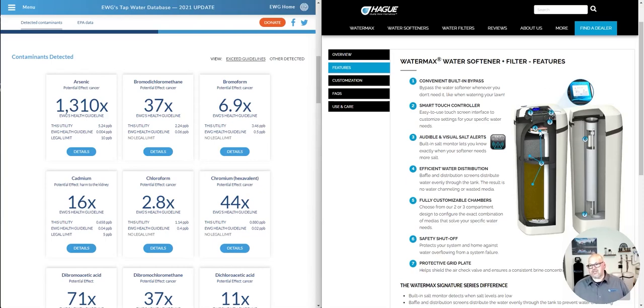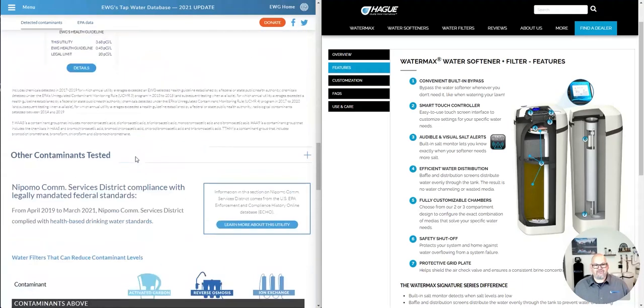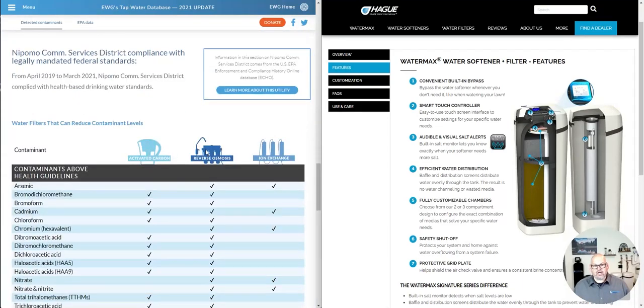So the idea is that this is physically filtering out everything larger than 20 microns so that it doesn't make it into the water system. But remember, the first step here is we filtered out the free chlorine by 95% immediately. In the second compartment, we have coconut shell granular activated carbon. Carbon is really great at absorbing chemicals. It's what you find in, again, this pitcher filter. That's full of carbon. Generally, at least two of the filters on reverse osmosis are also carbon.